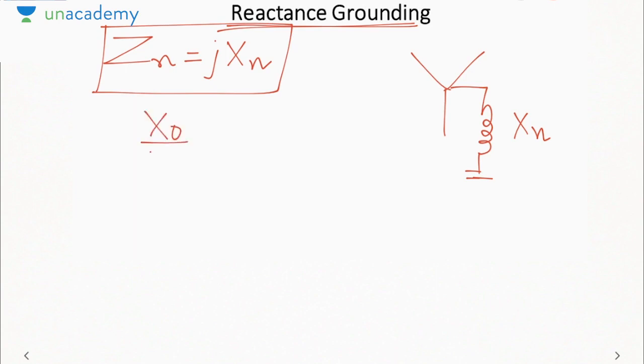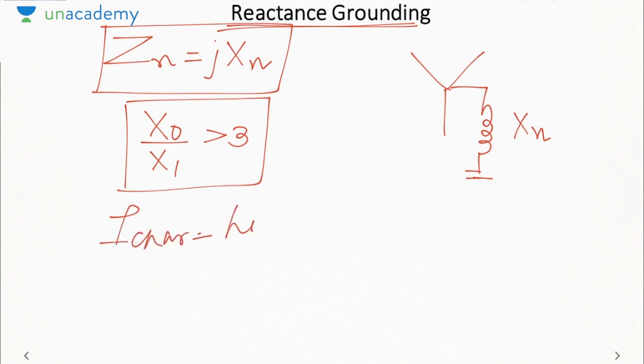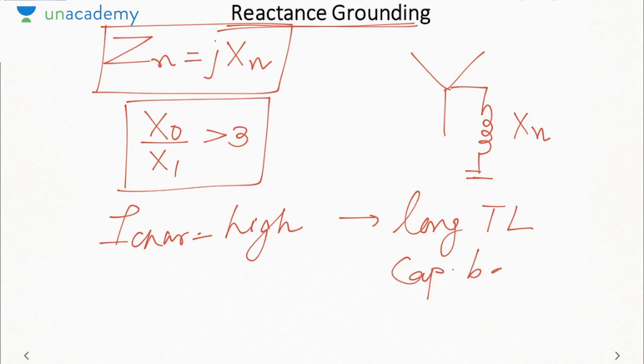Here X0 by X1 should be greater than 3 for the use of reactance grounding. Where to use reactance grounding? Wherever the line charging current is high. Where will the line charging current be high? It will be high for the case of long transmission line, capacitor bank, synchronous motor, because synchronous motor is usually operated at a leading power factor, so it will act as a capacitor. So whenever the system is having capacitor, line charging current will be high. We have to use the reactance grounding.